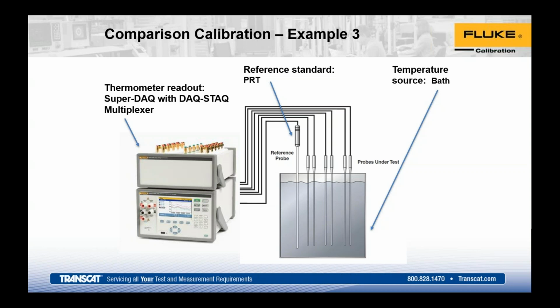But in this particular example, you can see we've got multiple devices under test, probably secondary or higher end probes, being compared to an SPRT with a multiplexer and then the reference. For manufacturing purposes, or customers in commercial labs that may be doing higher volumes, baths are typically utilized versus a dry well, which may be more suited for a factory floor, a quick check, or field use. It's just a little easier to transport: throw it in the car, the truck, or a cart and get it around the factory. So again, things to consider there in the process.